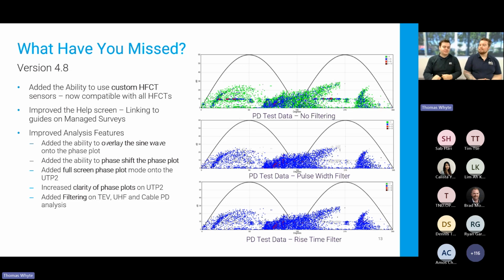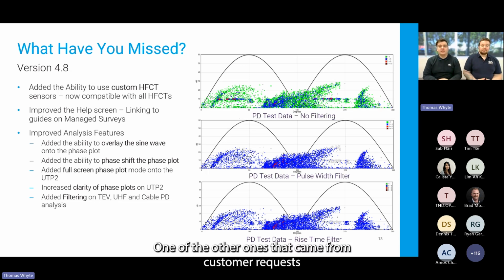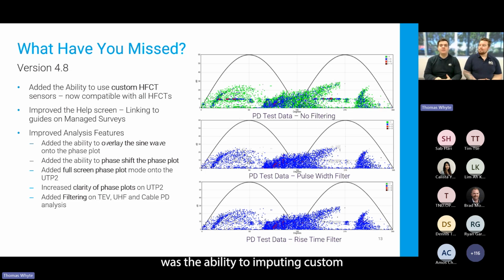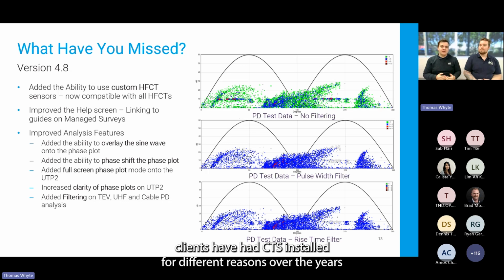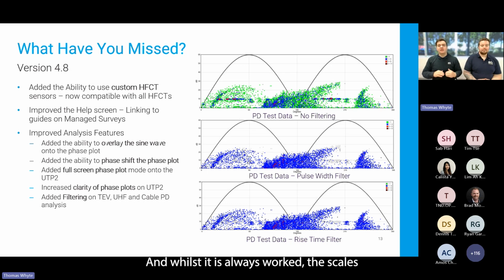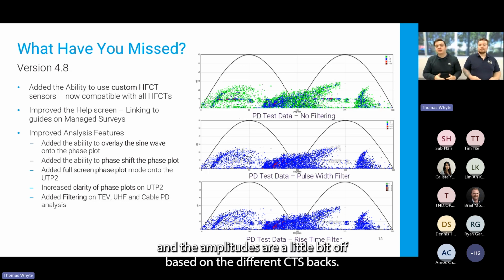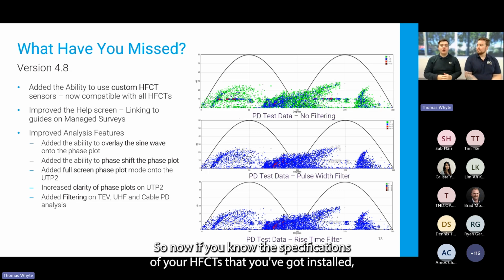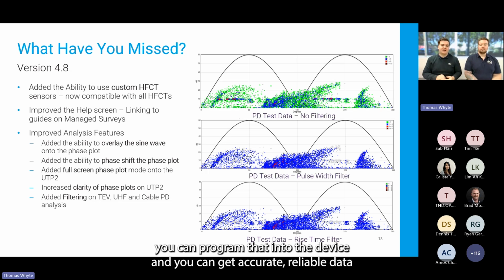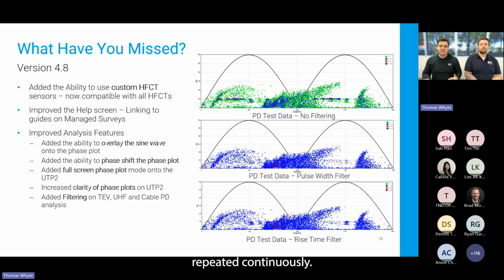One of the other features that came from customer requests was the ability to input custom HFCT features into the Plus². Obviously the device is primarily made to work with our HFCTs. However, a lot of clients have had CTs installed for different reasons over the years, and they wanted to use it with those CTs. Whilst it has always worked, the scales and amplitudes are a little bit off based on the different CT specs. So now, if you know the specifications of your HFCTs that you've got installed, you can program that into the device and get accurate, reliable data repeated continuously.